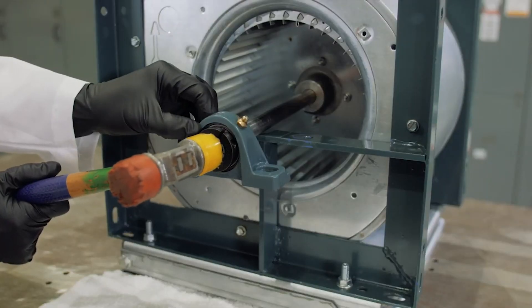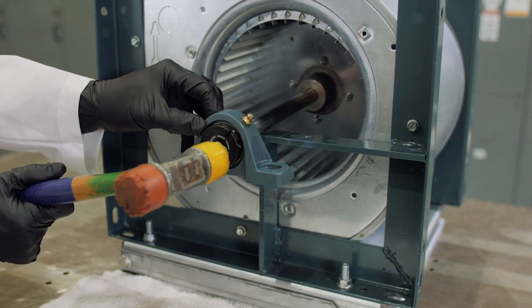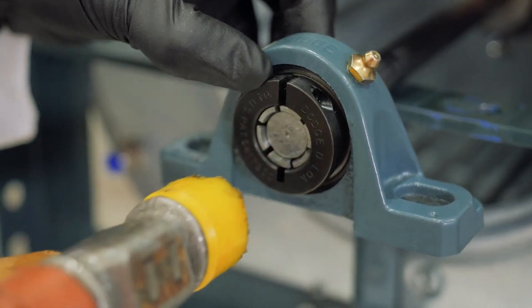Slip the bearing into the desired position. For tighter fits, tap the face of the inner ring with a soft driver. Do not strike the housing as this may damage the bearing.